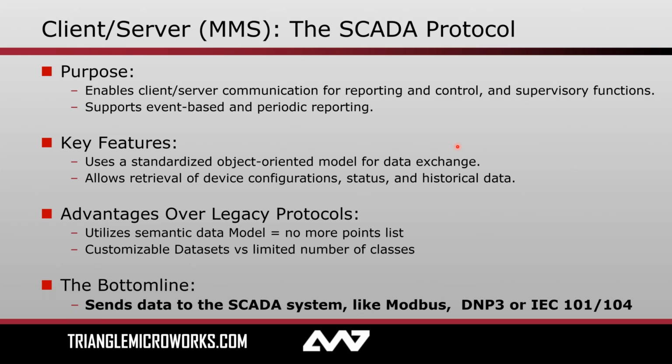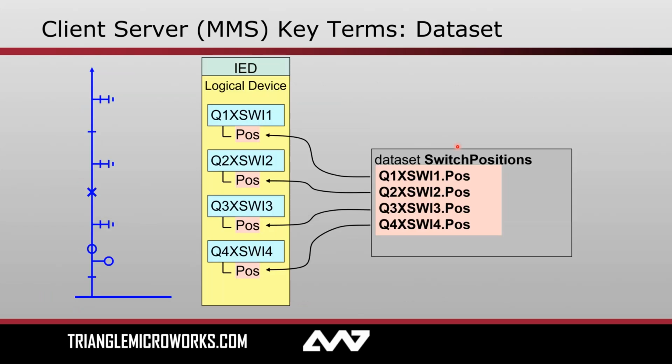So data set, that's a term that I just mentioned, and I want to dive in a little bit deeper about what it actually means. This is something that you'll have to do if you are a system integrator or utility who's designing a substation communication system. So a data set is just an opportunity for you to pick out what data you actually want to transmit.